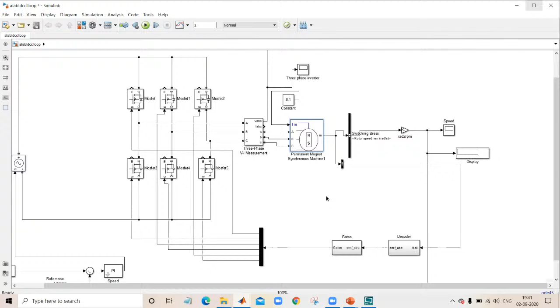So when I am connecting a bus selector here, this is a bus selector, and I connect it to this measurement port, automatically inside of the permanent magnet machine, this is the permanent magnet machine I said, right? Inside of that machine, for the rotor positions you need to identify, you compulsorily need to take the Hall effect sensor signal. Inside of the rotor we are placing the Hall effect sensors. Through those sensor signals only we will identify the rotor positions.